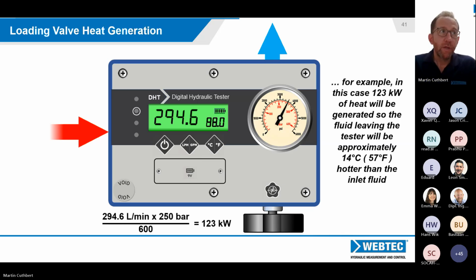If we do the maths on that, multiply the flow by the pressure and divide by 600, we get the power, in this case in kilowatts, 123 kilowatts, which is roughly equivalent to a 14 degree increase in temperature. It's not a problem, but it highlights that while you're loading testers, you're imitating the system working at full system pressure, and it will raise the heat in the system. You should only do that for a finite amount of time — you wouldn't want to leave it like that for hours.